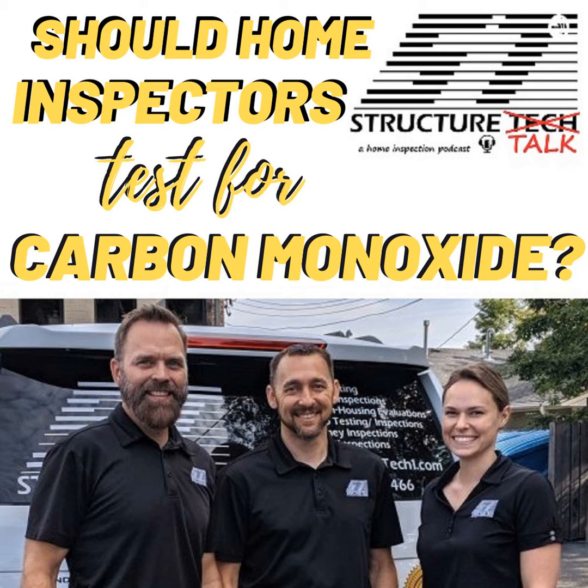It's at steady state. Can I ask a question? We just had an HVAC contractor come in and do a training session with us at one of our company meetings recently. Do you remember what he was talking about with doing that test at steady state on furnaces that have different modulations or stages, I should say? Well, if it's a 2-stage furnace, and we see a lot of those, it's best to do the test when the furnace is on the second stage.